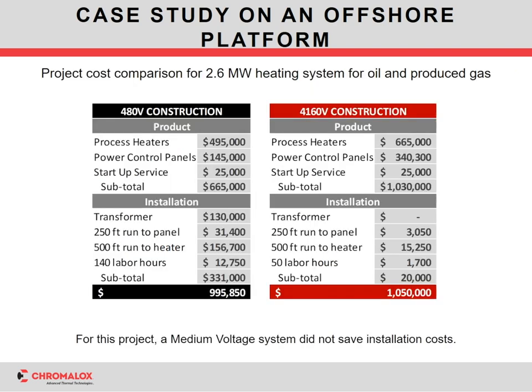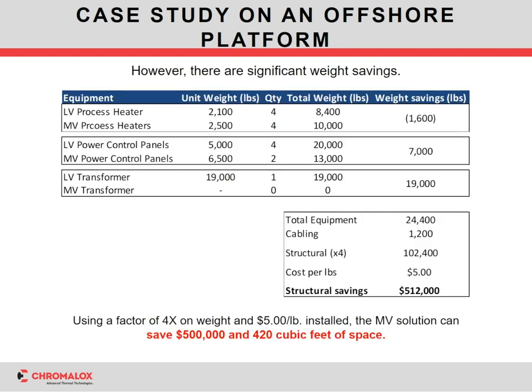So as we started to look through the price analysis for this customer, interestingly enough, it came out that medium voltage, despite the lower cost of wiring, wasn't necessarily the lowest overall cost on the installation. And what that came down to, again, was a lot shorter runs of power wiring needed due to the compact size of a platform. However, although the installation savings didn't show an immediate benefit one way or the other, it really came down to the weight and the size of the product that was going to be installed on the platform. So interestingly enough, when you actually look at the weight of a medium voltage system as compared to the heater, the control panels, the transformer, and even the wiring itself, that's where it was able to make a difference for the customer.